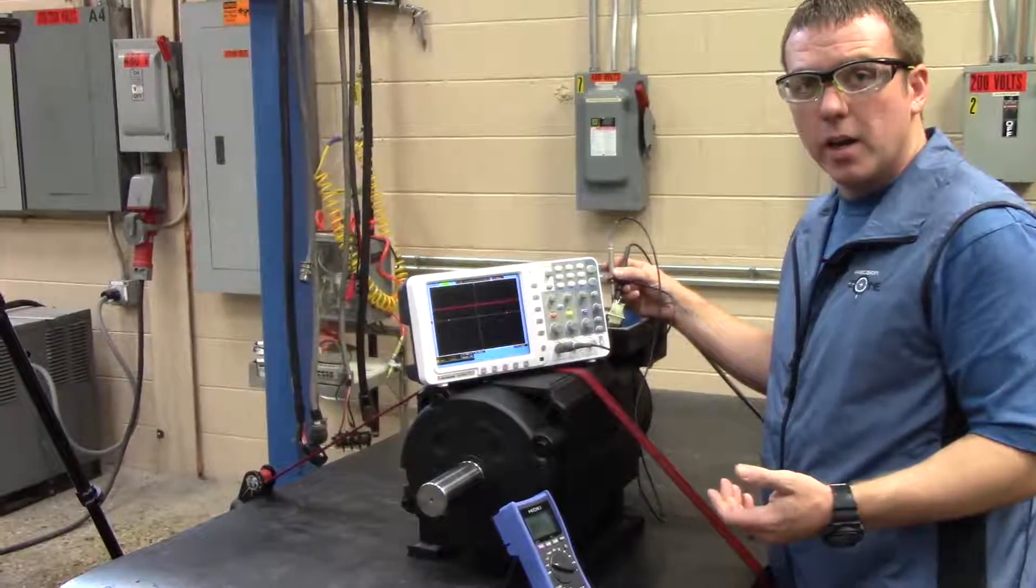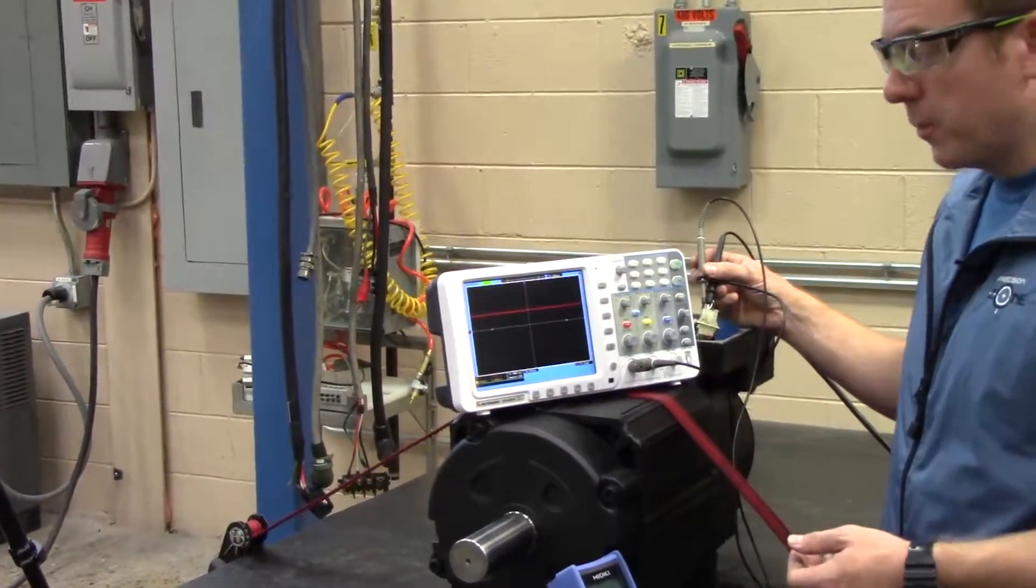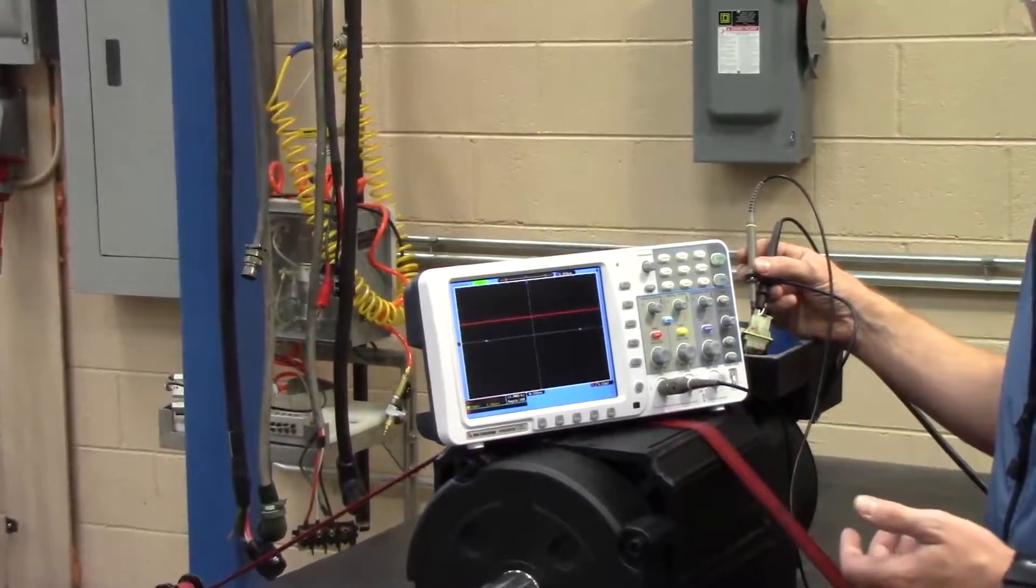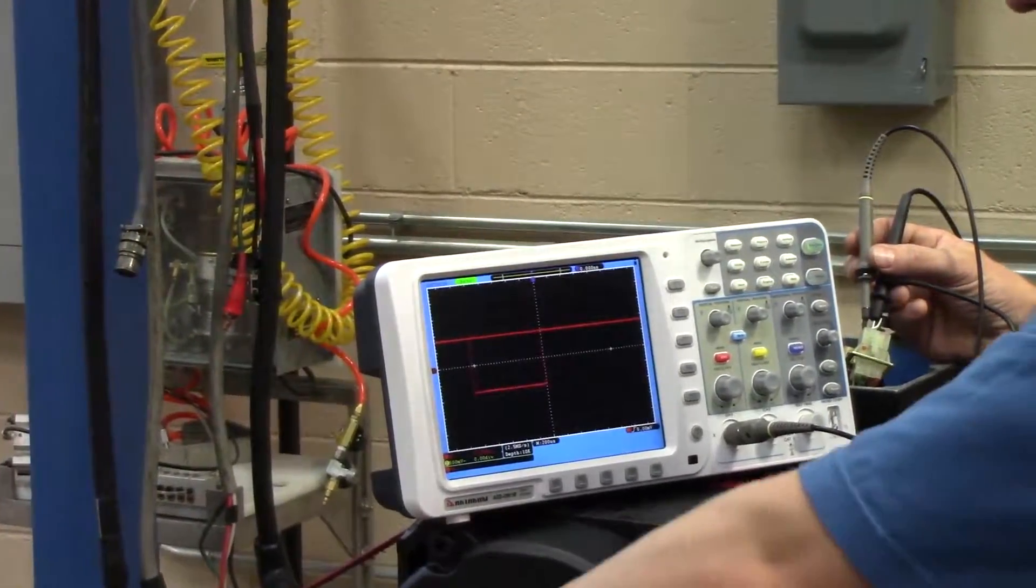Now if your machine is running, but it's not orientating, it may have lost its Z signal. Now Z is a lot harder to find than A and B, but keep trying and adjusting your scope.